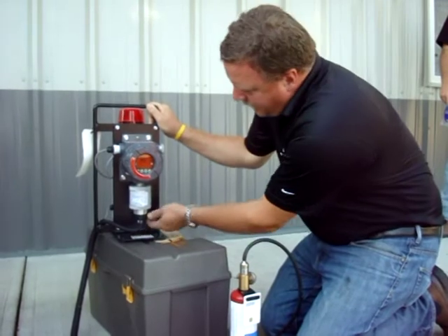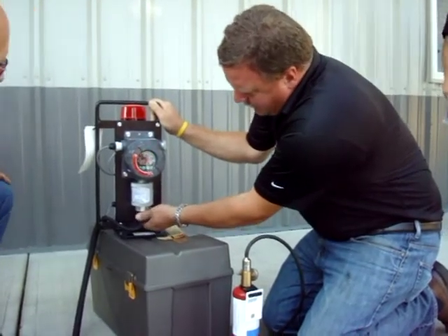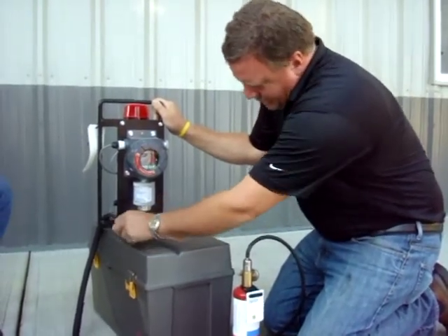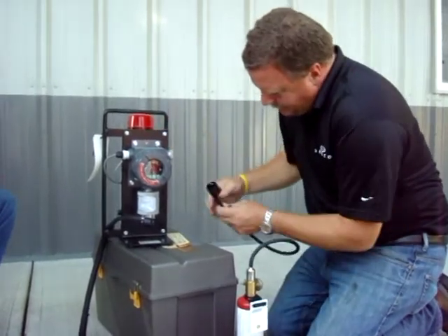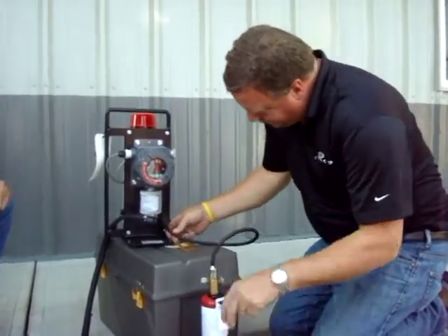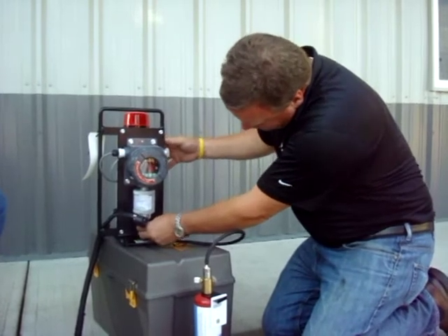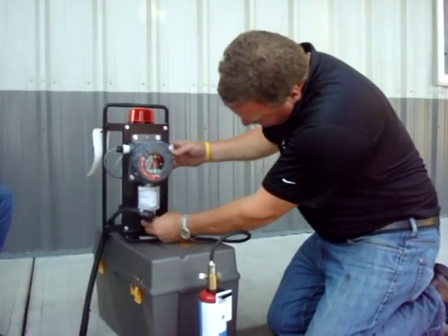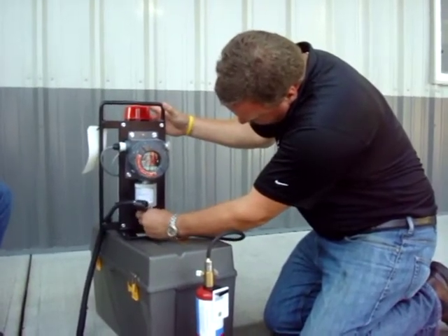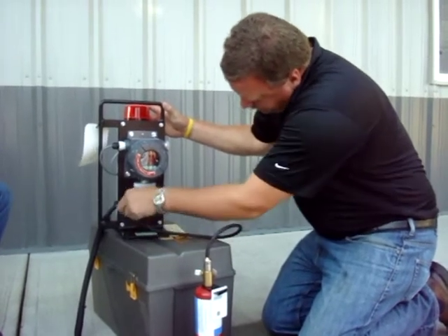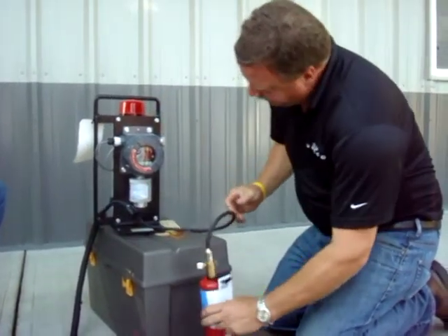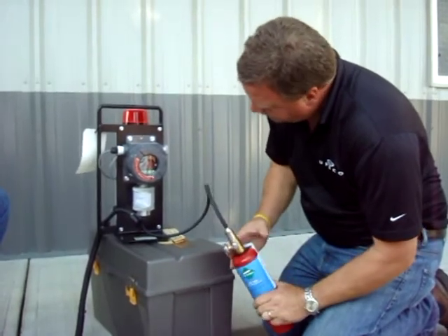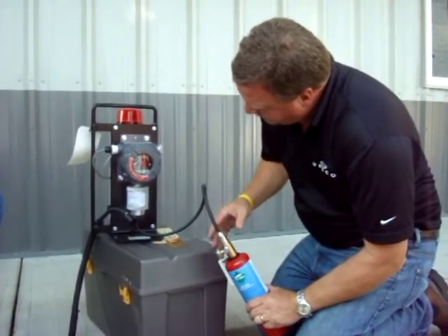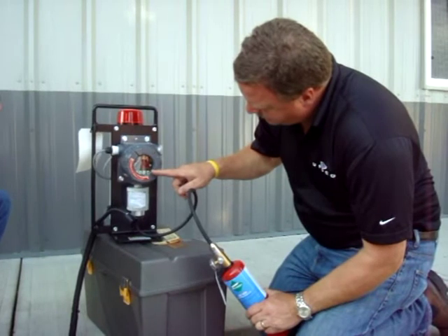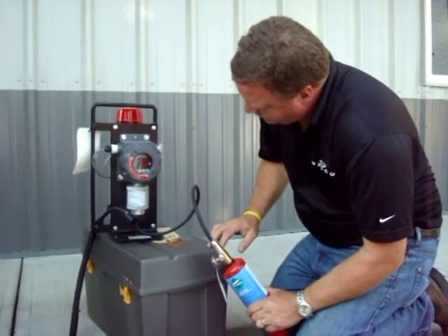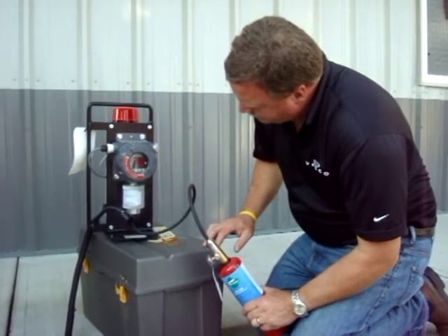The bottom cup. We've got to remove the bottom cup? Yep, remove the bottom cup. Make sure that the meter is set to the calibration gas you are using. This is 50% LEL methane, and you need to make sure that the span gas on the meter is set to that as well. Put the cup on the bottom of your meter, from your gas tank, and again when it gets to about 60, turn the gas on, and you will see this top line count up.